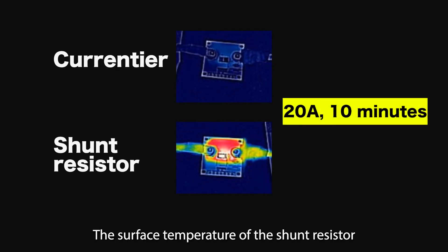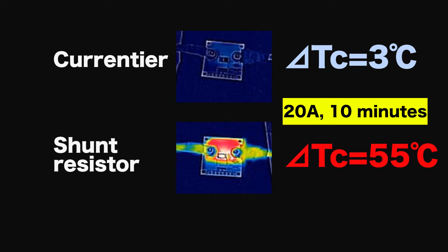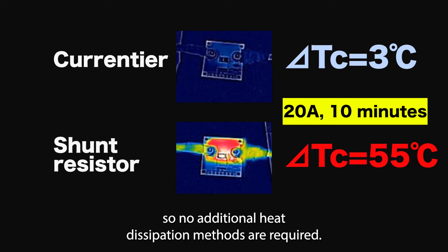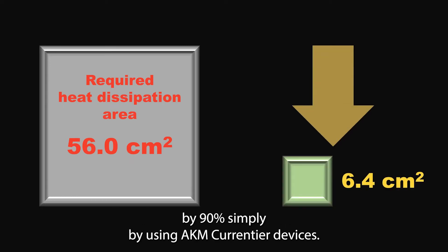The surface temperature of the shunt resistor has risen by 55 degrees Celsius, which means that bulky heat sinks and/or fans may be required for cooling. The temperature of the AKM device has only gone up by 3 degrees Celsius, so no additional heat dissipation methods are required. It's possible to reduce the area required for operation by 90% simply by using AKM Currentier devices.